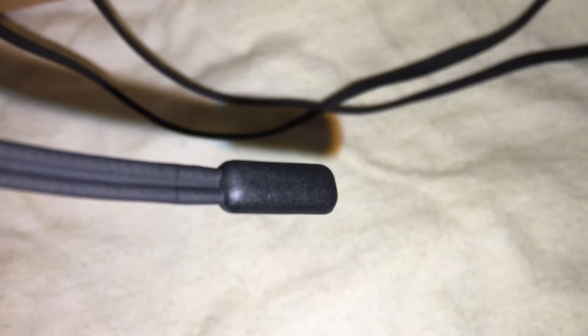Looks pretty darn nicely sealed up. You could put it inside of a piece of copper - stick a piece of 3/8 copper over it, then stick that piece of 3/8 copper in an evap. I don't think I'd want to stick the sensor in an evap by itself - it would work, but I don't know for how long. That's how you could control by coil temp.